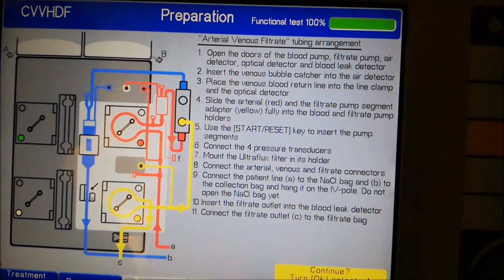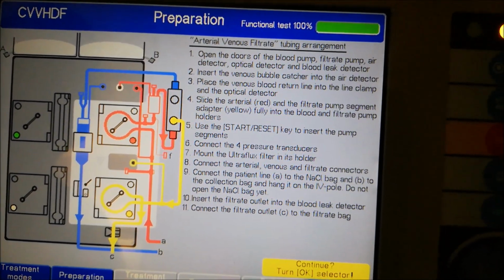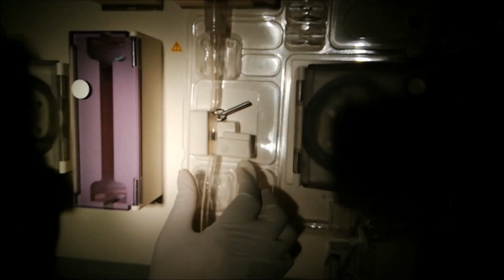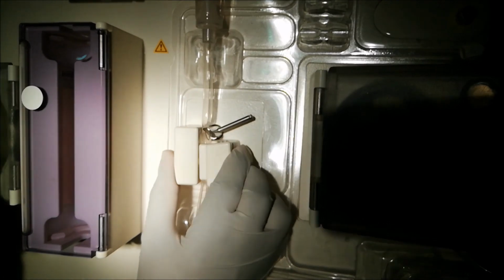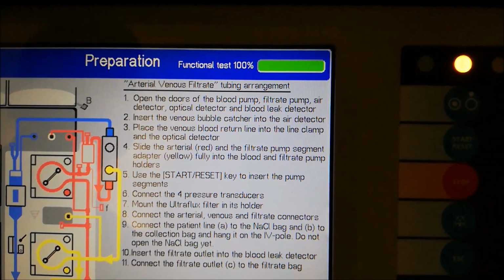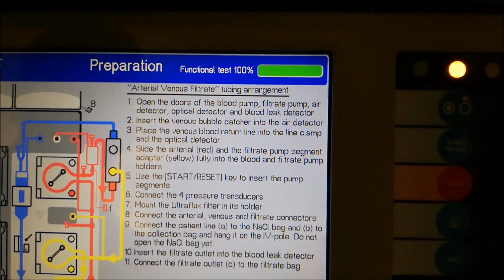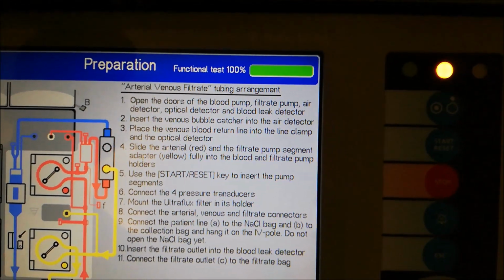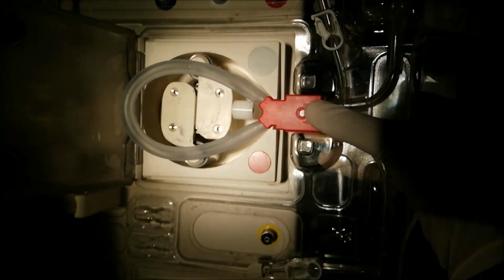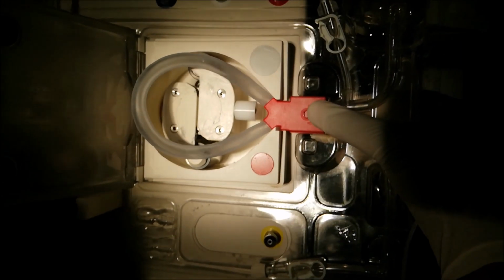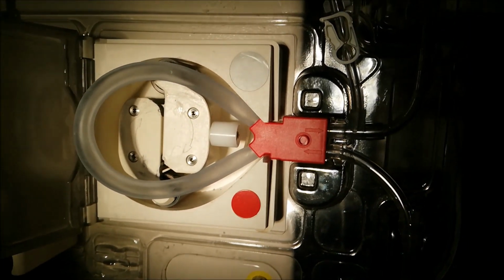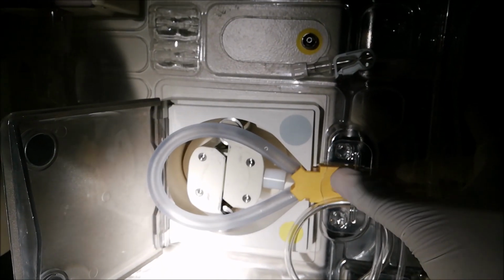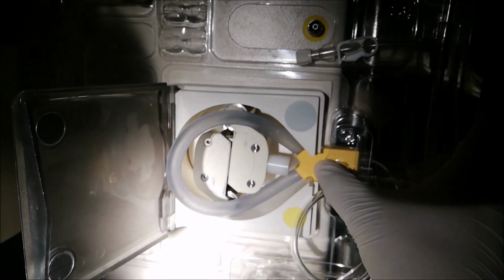Place the venous blood return line into the line clamp and the optical detector. It is venous return line. We have to open the clamp and insert venous line into optical detector and close the optical detector. Slide the arterial red and the filtrate pump segment adapter yellow fully into the blood and filtrate pump holder. Now inserting arterial tubing into blood pump. We are inserting filtrate tubing into filtrate pump.